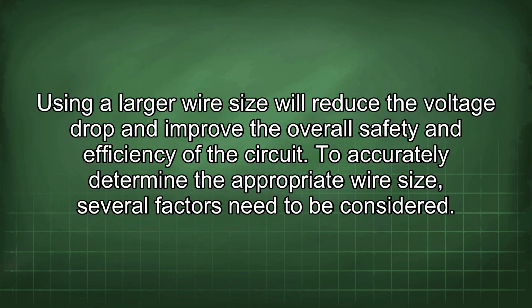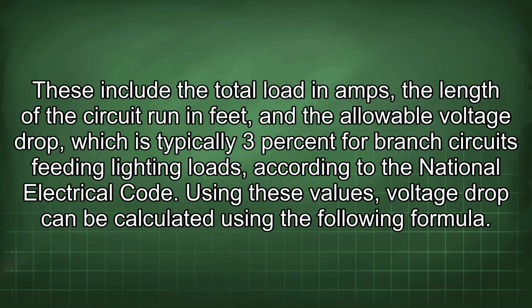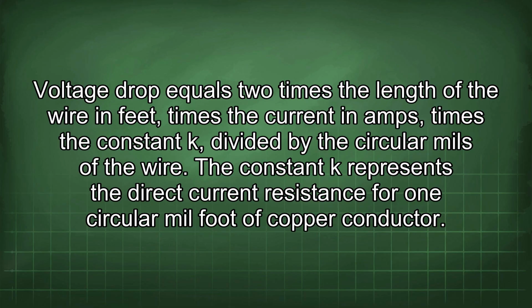To accurately determine the appropriate wire size, several factors need to be considered. These include the total load in amps, the length of the circuit run in feet, and the allowable voltage drop, which is typically 3% for branch circuits feeding lighting loads according to the National Electrical Code. Using these values, voltage drop can be calculated using the following formula. Voltage drop equals 2 times the length of the wire in feet times the current in amps times the constant K divided by the circular mils of the wire.